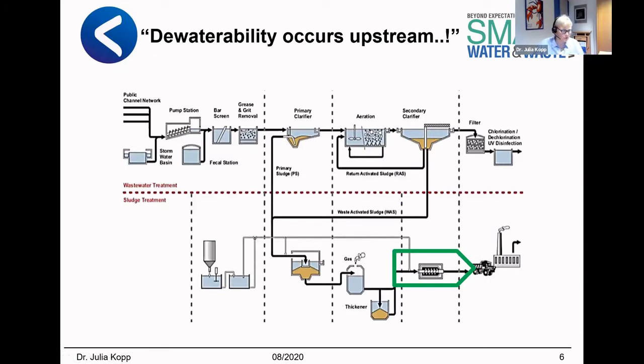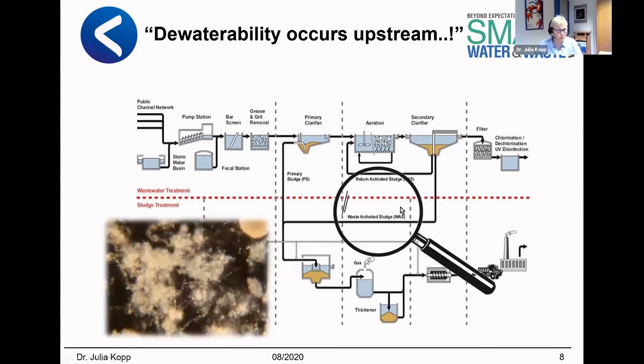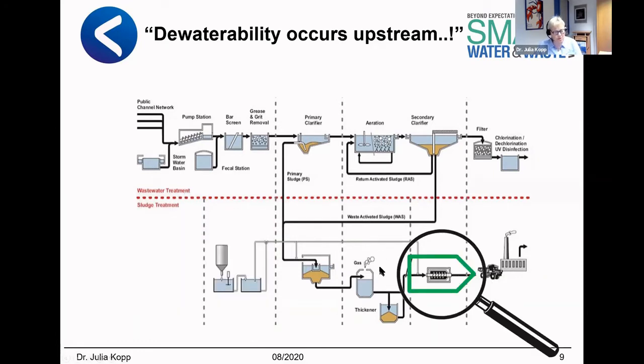Here you see a flow chart of a wastewater treatment plant, and we talk about this piece: the mechanical dewatering at the end of the process. The characteristics of mechanical dewatering — the dried solid you can achieve — are related to the ratio between primary sludge and waste-activated sludge. Primary sludge is very fibrous, with small particles, easy to degrade, and not a troublemaker. But if you have a short retention time in your primary clarifier, you get more waste-activated sludge, which is mostly bacterial, more jelly-like, with quite high water binding.